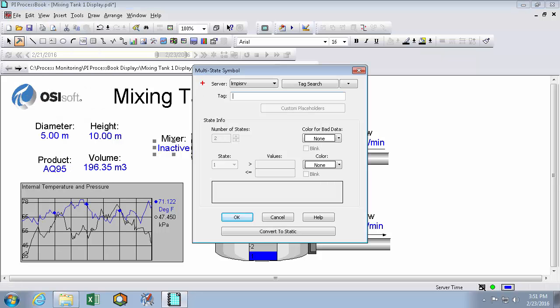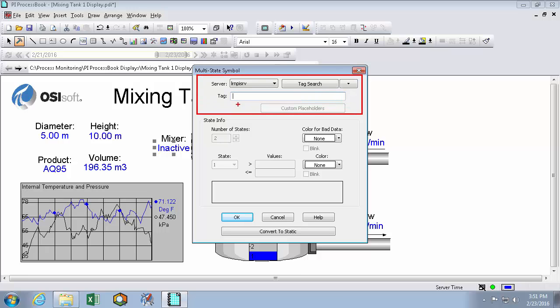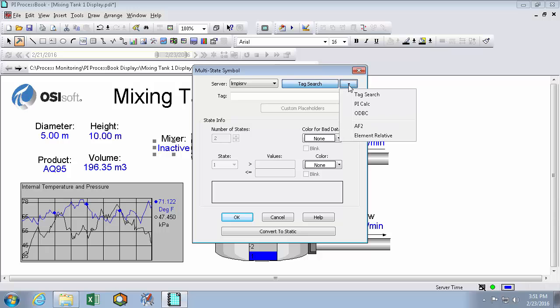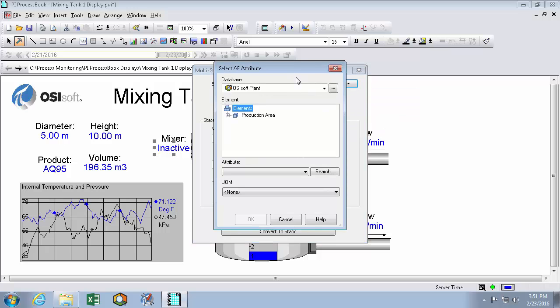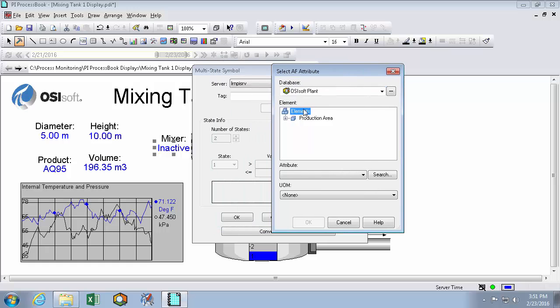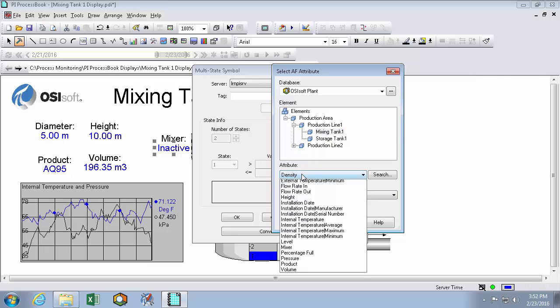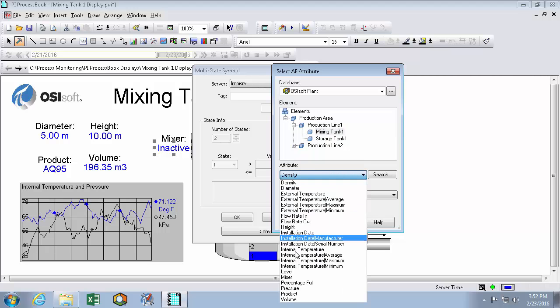Here the first thing to do is select the data source that your multi-state is going to trigger off of. If you know the PI point you can type it in there or search for it there. But since mixing tank 1 is in my AF structure, I'm going to use this pull down menu to search my AF tree. I know it's in production line 1 and there it is. And we'll set the attribute to mixer.